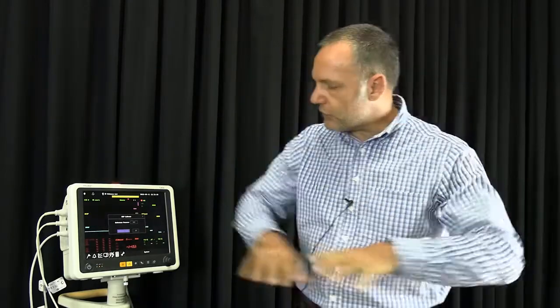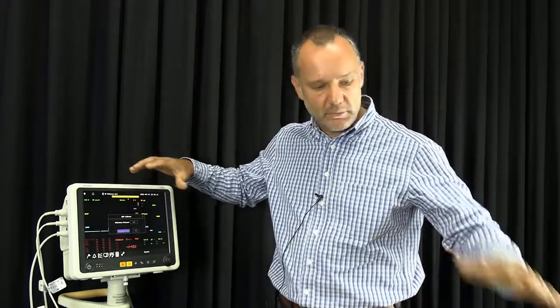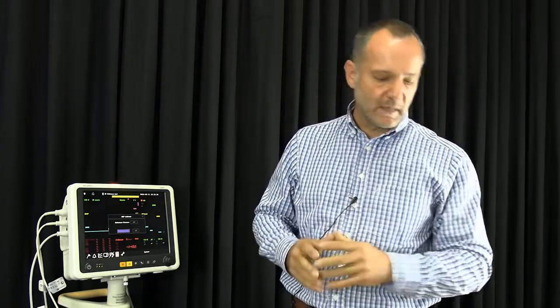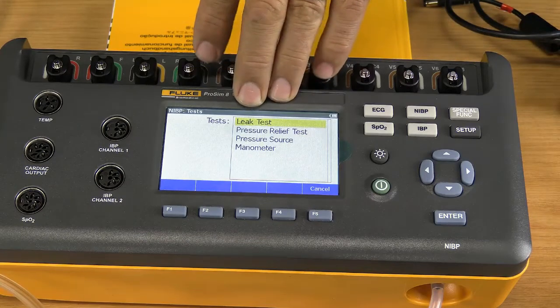The first one is a leak test. Now, what we do during a leak test is we are pressurizing the whole system from the cuff to the inside of the patient monitor and everything in between. And then we close the valves and we measure over a period of 60 seconds, 120 seconds, depending on your service manual, what the pressure loss in the system is. That will give us an idea whether the integrity of the whole circuit is in good order. Okay. The second one is our pressure relief test.